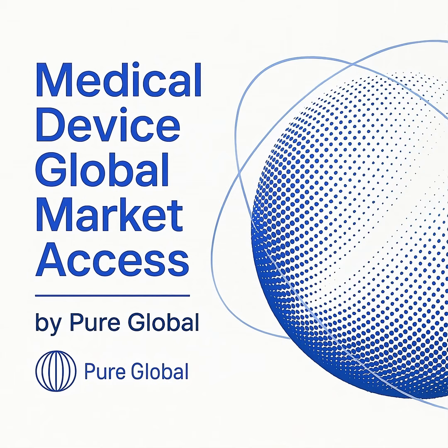So what practical actions should your team take now? First, we recommend conducting a detailed gap analysis. Compare your current technical file and testing data against every recommendation in this new guidance to identify any shortfalls. Second, engage with your material suppliers immediately. Begin the conversation about obtaining the detailed chemical characterization and biocompatibility data that the FDA now expects.